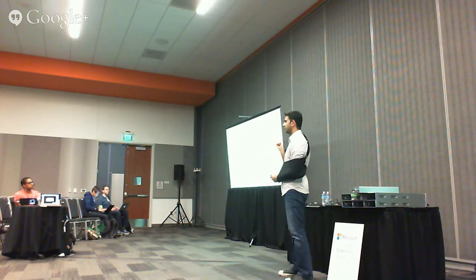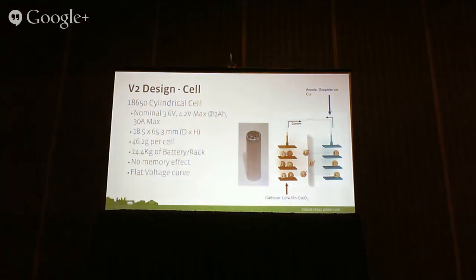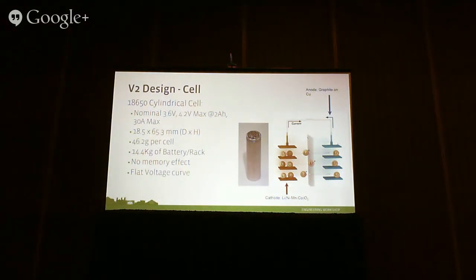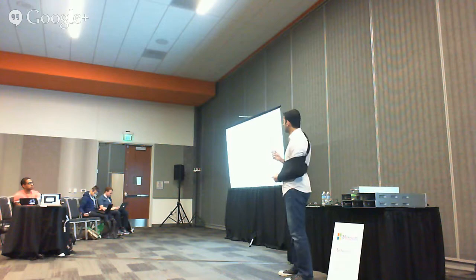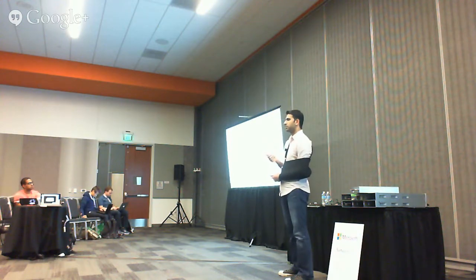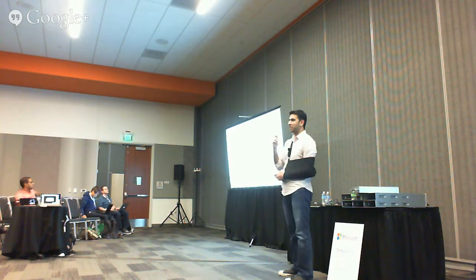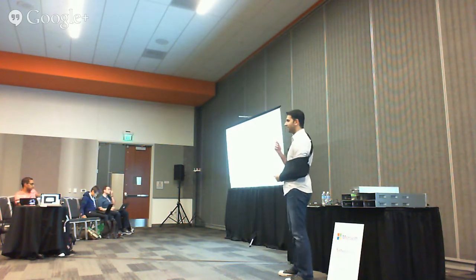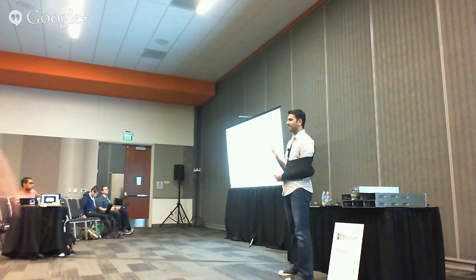So with that, we'll jump into the design itself. The goal is to get rid of the lead-acid battery and use this instead - these are pretty much the cells used in Tesla, for example. They're 18650 cylindrical batteries; for those familiar with batteries, 18650 refers to the size, roughly 18 millimeters by 65 millimeters. They're nominal 3.6 volts, maximum 4.2, 2 amp hour batteries - pretty standard. What's not standard is they can discharge up to 30 amps maximum, and they're 46 grams each. If you multiply that out, it's 14 kilograms per rack worth of batteries - lighter than one lead acid battery.